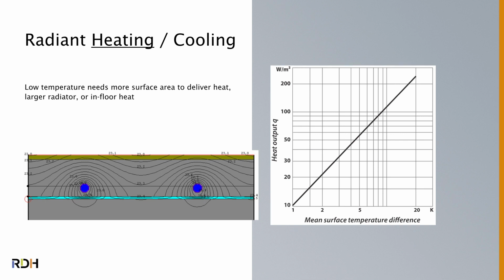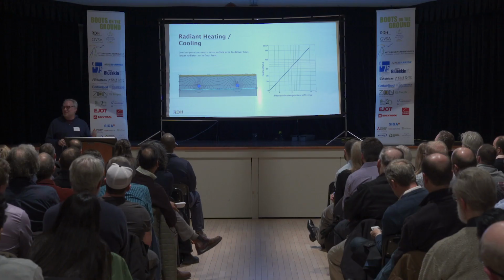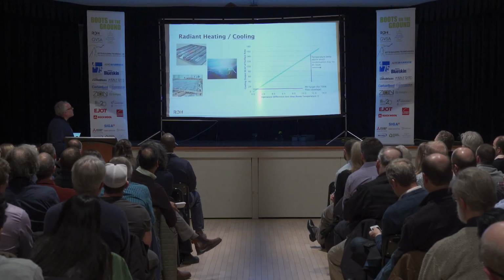Now, that's more than you need, but you don't get all the floor space because people like to put furniture on the floor, and radiant heating systems only heat what they see. So you've got to derate that somewhat, and we're only providing 24, 25-degree water to these pipes. You can do that with solar thermal. Put some solar thermal on the roof.